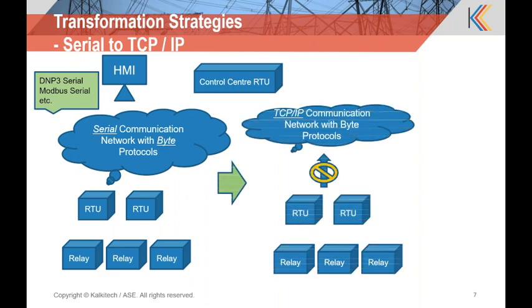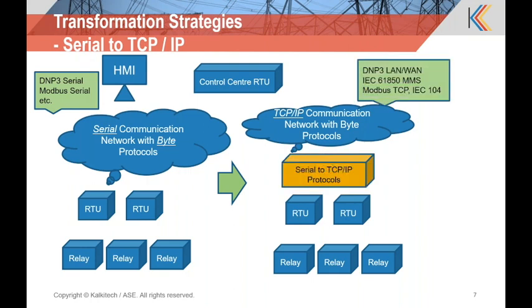This simplifies asset management ultimately because you'll have one device that can operate as multiple masters with our given solution. Here we have DNP3 or serial Modbus information from the field mapped to the DNP3 LAN-WAN equivalent, IP equivalent, or 61850. Regardless of the protocol, we can map from one library to another to give you the data point in the format that you seek.